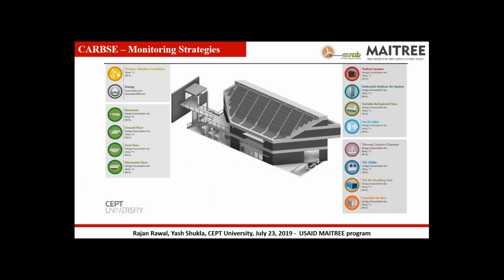This is a screenshot of our building management system. We could not actually get the kind of graphics and interface that we were looking for to effectively operate our monitoring system, so our in-house team designed this interface for the building management system. In here, the top box on the left side shows the outdoor conditions and the entire building energy consumption. So you'll see the outdoor weather station conditions and energy is the focus of that box.